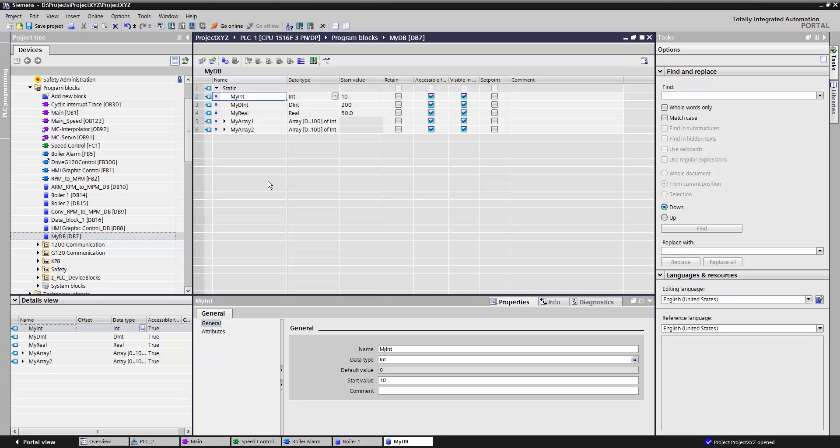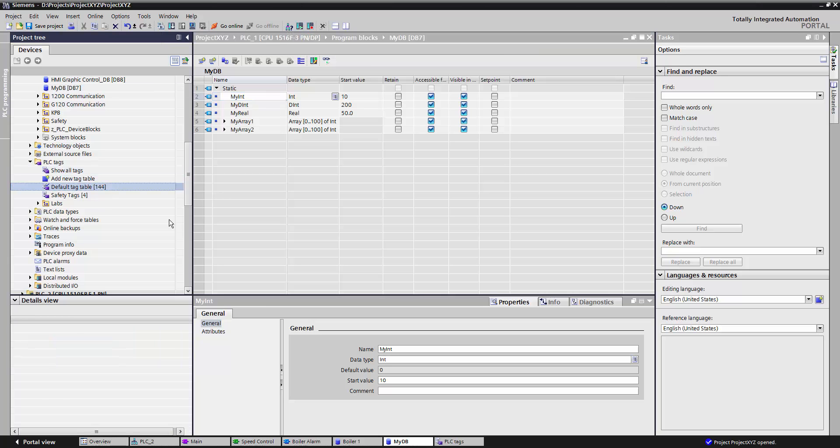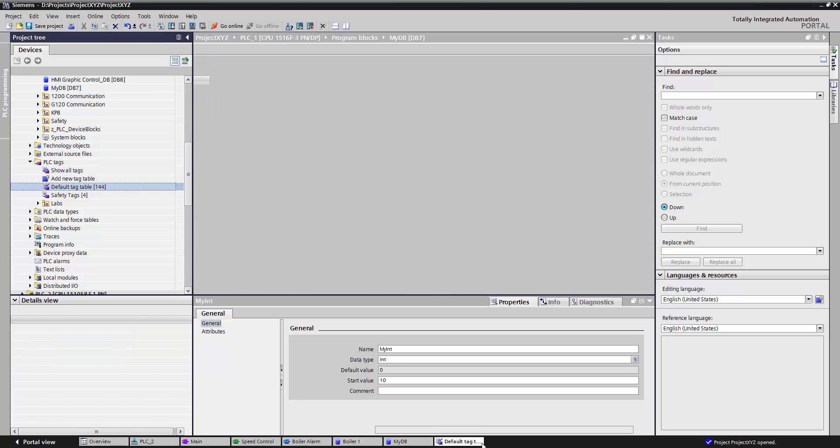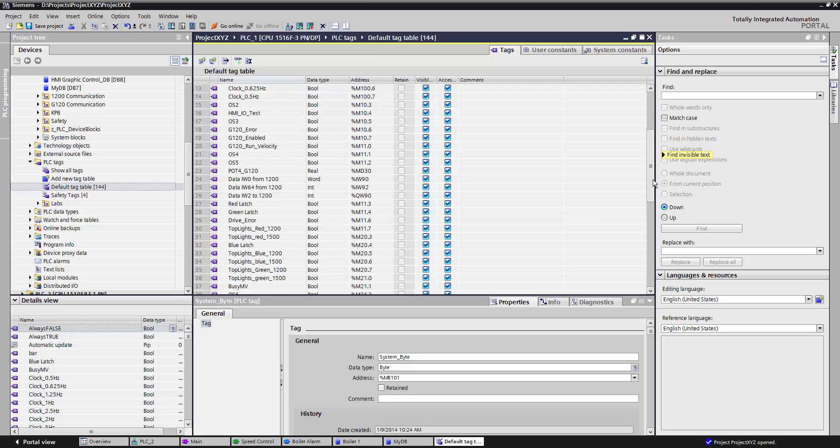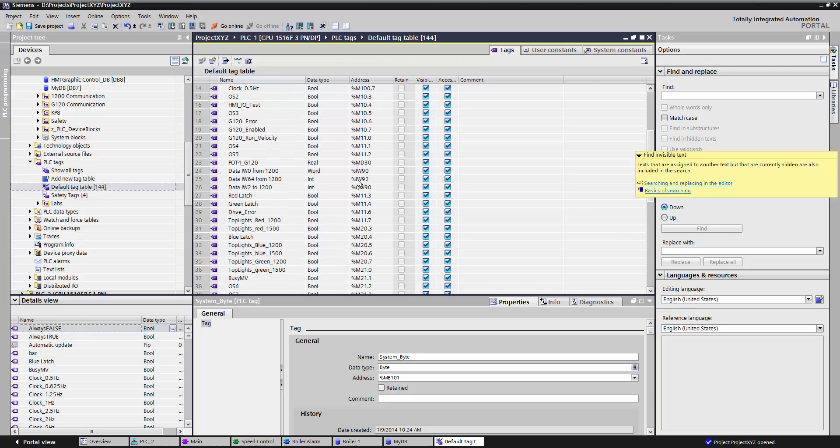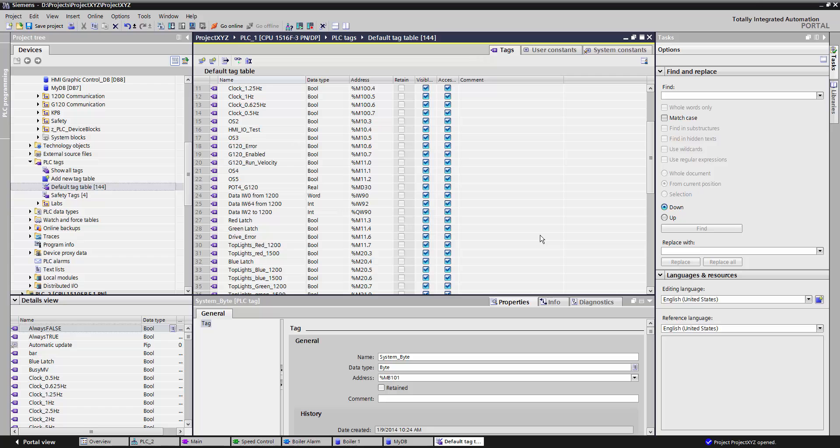The data block is one of two areas where data can be stored in your PLC. The other area is under PLC tags. PLC tags are where your inputs and outputs are stored. Your inputs are indicated by this I address, and your outputs are indicated by a Q address. This is also where your RAM memory or working memory gets stored, and that's indicated by an M address.